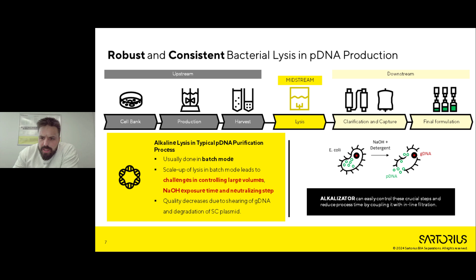Here on the left side, we see the machine as it is, and on the right side, we see a schematic that I will go through. We have 4 peristaltic Watson-Marlow pumps. We also have 3 pressure sensors and 4 ultrasonic flow sensors. First, you start pumping cells and sodium hydroxide, so basically pump orange and blue. This is then pumped and mixed through the first mixer. This mixer has high shear because you have 2 solutions that are different in viscosities, so you need efficient mixing. So mixing cells and lysis buffer.